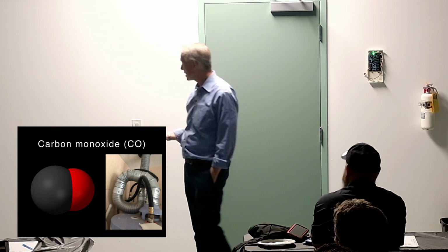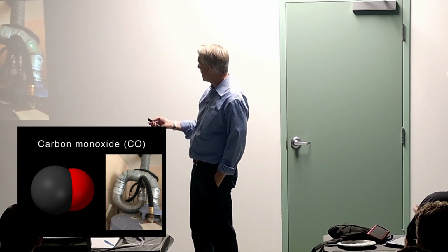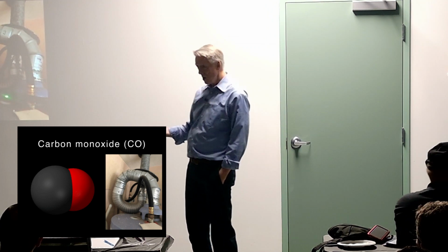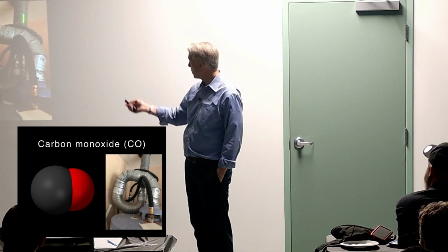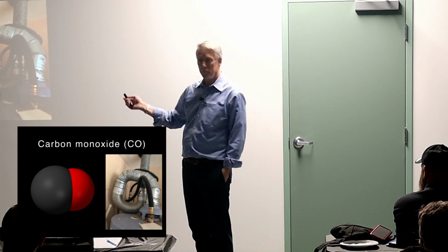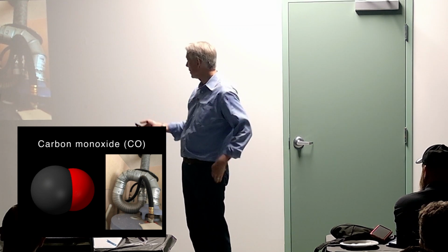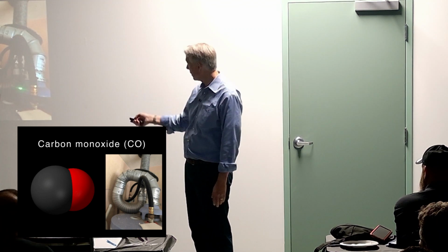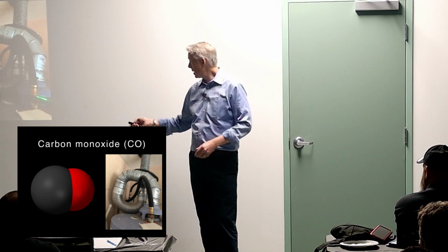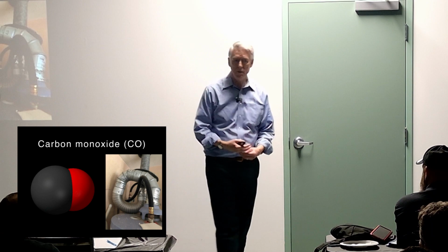This is inside the building enclosure somewhere, and so the flue gases are supposed to come up and then go outside. But if they have to go down at all, you get a plug of cold air in wintertime that's going to sit there, and those gases are not going to be able to go down. They can go up because they're lighter than the air around them, but when you get that plug of cold air in there, it's going to sit there, and that means all the flue gases are going to get out from under this draft diverter and into the air in the house.